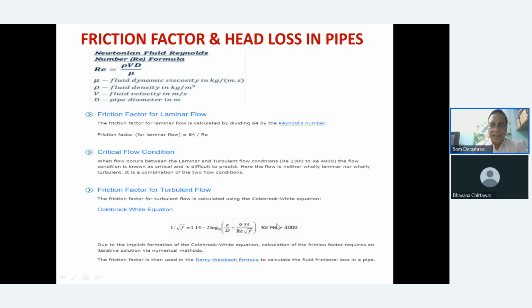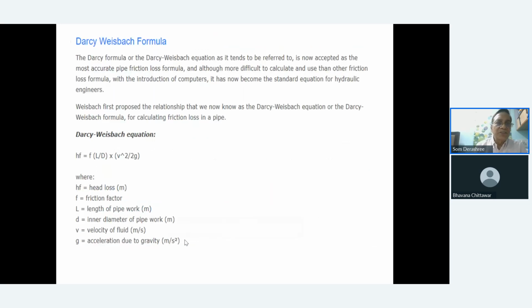This is a typical equation for the friction factor, but it's a little complicated mathematics that we have to do. So better to go in for another method, let's say Moody's chart. Or first you come to the Darcy-Weisbach formula. What is done here: the Darcy-Weisbach formula gives the head loss, and this is the friction factor F, which we can find either through this equation or from the chart, which is much more easily available.